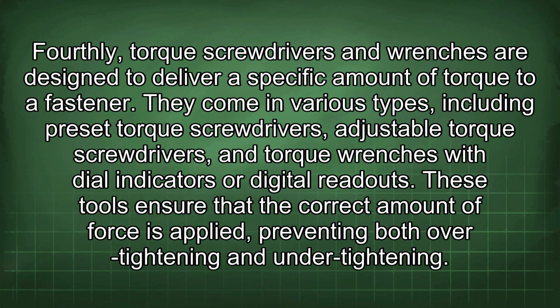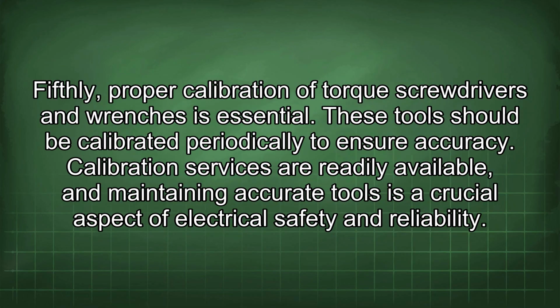Fourthly, torque screwdrivers and wrenches are designed to deliver a specific amount of torque to a fastener. They come in various types, including preset torque screwdrivers, adjustable torque screwdrivers, and torque wrenches with dial indicators or digital readouts. These tools ensure that the correct amount of force is applied, preventing both over-tightening and under-tightening. Fifthly, proper calibration of torque screwdrivers and wrenches is essential. These tools should be calibrated periodically to ensure accuracy. Calibration services are readily available, and maintaining accurate tools is a crucial aspect of electrical safety and reliability.